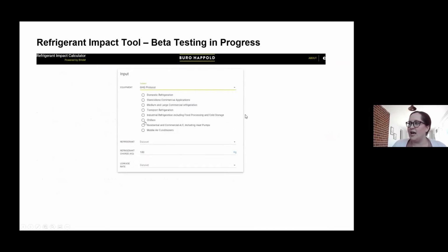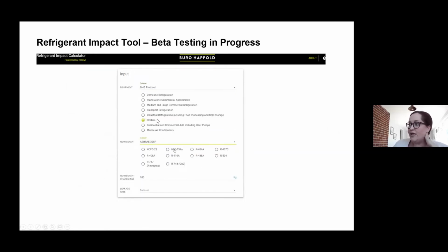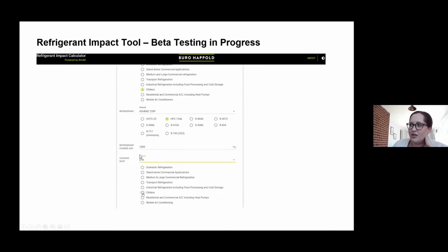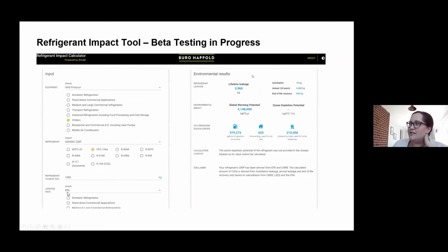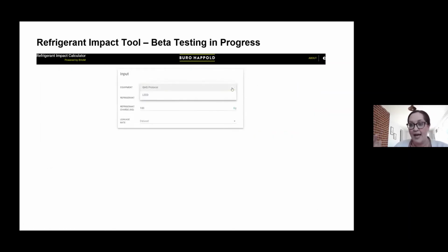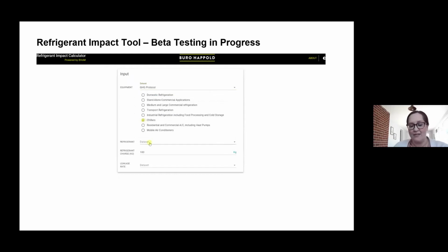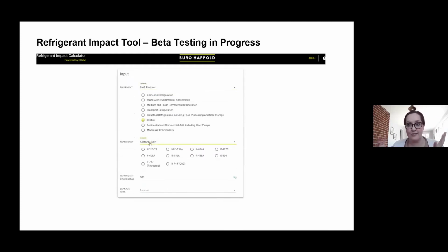So BH has used our open source code-based BOM that Luke mentioned to create a tool that requires zero code. It has all these databases plugged into the back end of it. So you can choose your equipment type. This determines the lifespan. You choose your refrigerant. We'll choose 134A for this chiller, give it the charge, and then tell it the leakage rate that you'd like to utilize. And it gives you the lifetime leakage, allows you to see that total global warming potential, and allows you to see the EPA equivalencies. We are in the process of creating some comparison features on this as well, so that you can compare R134A to R410A to 1234ZE, as well as comparing, let's say you're deciding between 1 chiller and 20 VRFs, being able to compare those different equipment options for your building.